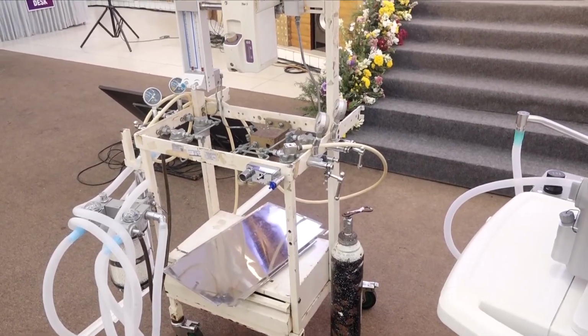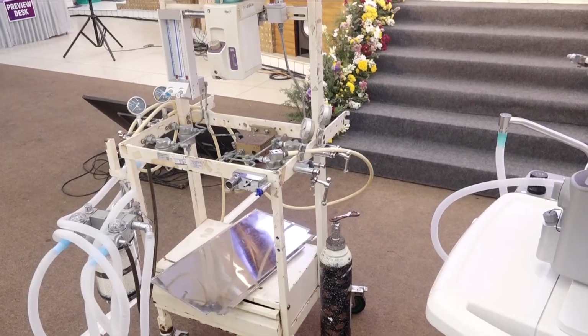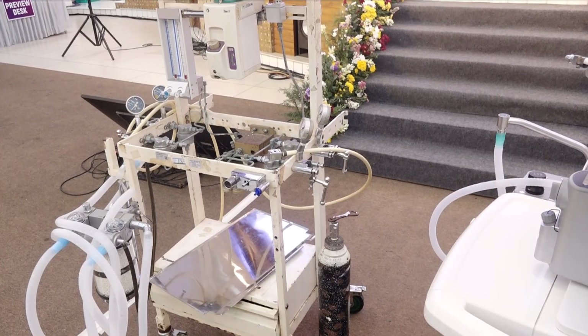This is an important exam question, because it's a safety feature: why is there a difference between the cylinder pressure reduced to 45 psig and pipelines at 55 psig? What you do every day when you come is first open the cylinder, especially the oxygen, because these cylinders are used as a backup source of oxygen and nitrous oxide. Actually, they are not directly used for providing anesthesia every day.